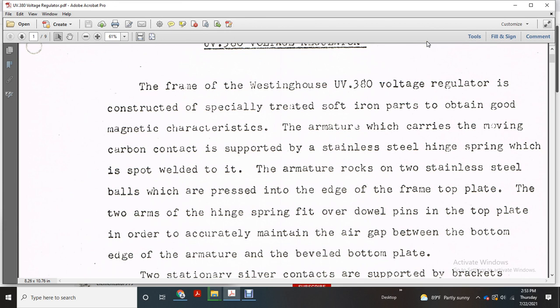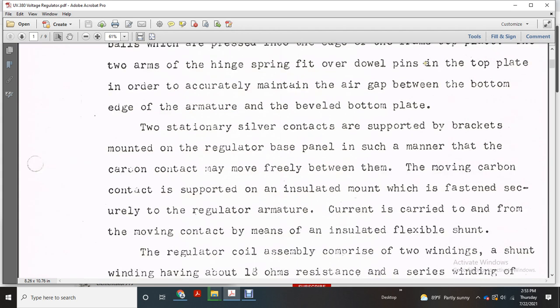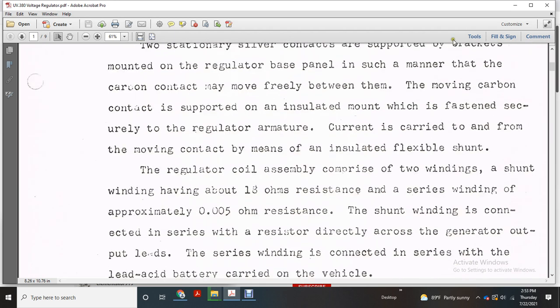the top plate. Two arms of the hinge spring fit over the dowel pins to the top of the plate in order to accurately maintain the air gap between the bottom of the edge of the armature and the bevel bottom plate. The stationary silver contacts are supported with brackets mounted on the regulator base panel in such a manner that the carbon contact may move freely between them. The moving carbon contact is supported by an insulated mount, which is fastened securely to the regulator armature. The current is carried to and from the moving contact by means of an insulated flexible shunt.